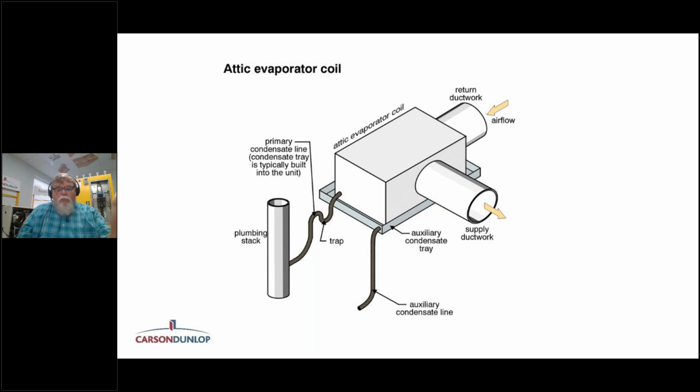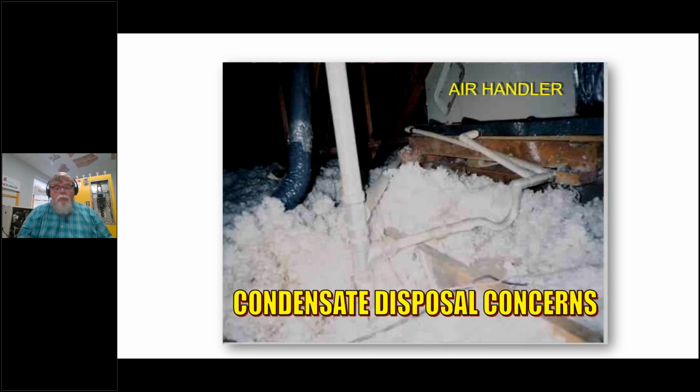So pretty much all the localities I see out there, they say, hey, look, don't do this in the stack. And I actually have an image of one right here. If you look at this, there's an air handler sitting on a platform over a pan. The condensate will actually drain to the line here into the stack, and it's going to go down the stack, so it's going to end up in the sewer. It's going to flow into the city sewer, but the sewer gases flow through this pipe out through the vent.